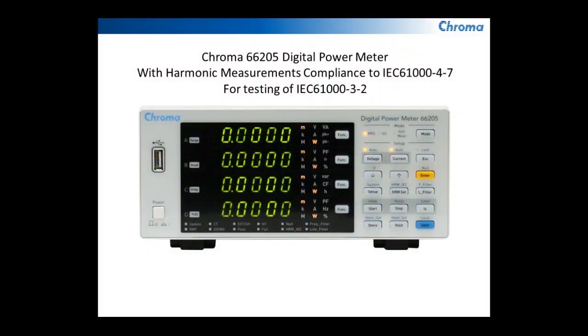Hi, I'm going to be talking today about the Chroma 66205 digital power meter, and specifically the ability for it to measure harmonics. Chroma designed this unit to meet the IEC 61000-4-7 standard, and that standard defines what the equipment capabilities must be when testing devices for IEC 61000-3-2.